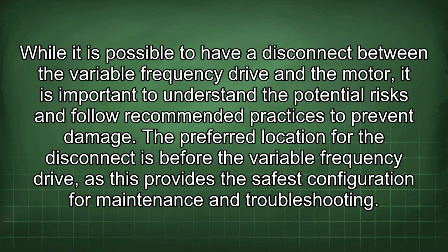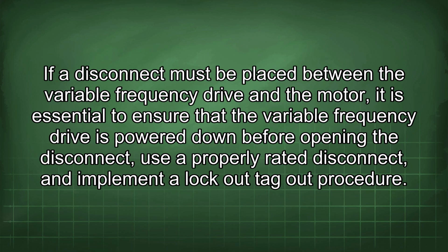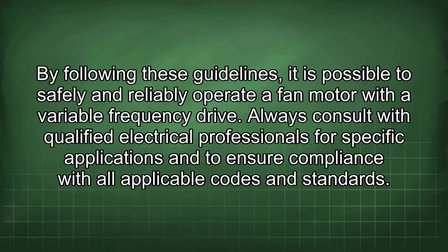The preferred location for the disconnect is before the variable frequency drive, as this provides the safest configuration for maintenance and troubleshooting. If a disconnect must be placed between the variable frequency drive and the motor, it is essential to ensure that the variable frequency drive is powered down before opening the disconnect, use a properly rated disconnect, and implement a lockout-tagout procedure. By following these guidelines, it is possible to safely and reliably operate a fan motor with a variable frequency drive. Always consult with qualified electrical professionals for specific applications and to ensure compliance with all applicable codes and standards.